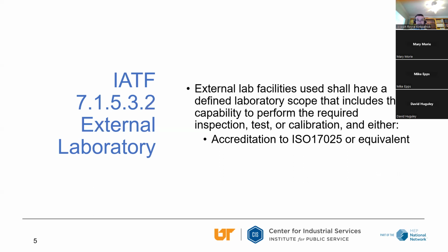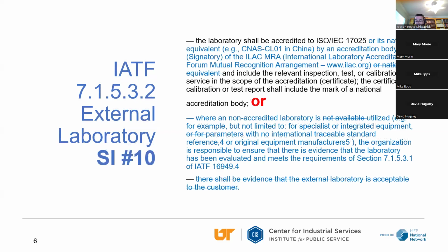External labs. If we use any external labs for testing or calibration, these labs need to be 17025 or equivalent. There are some sanctioned interpretations that have come out on this requirement in the IATF standard, and they did say you can use a 17025 or a national equivalent, and you've got to have the certification mark of the body on the certificate or the test report. There's a big "or" that came out, and this "or" is very important for anybody in the laboratory or using outside labs to understand.